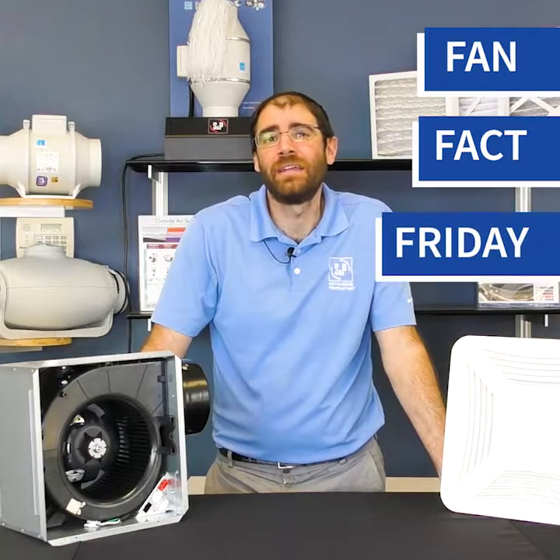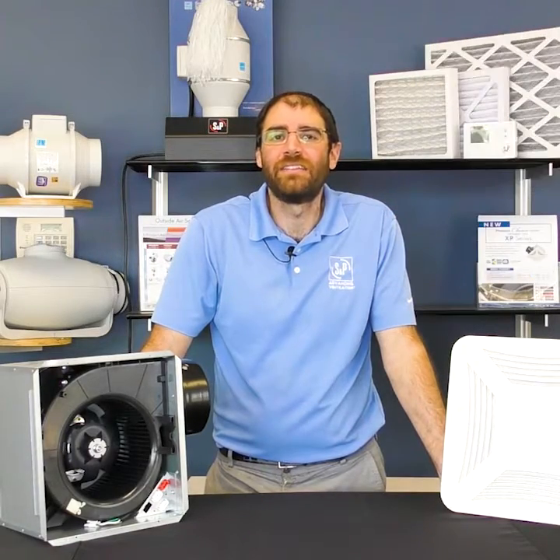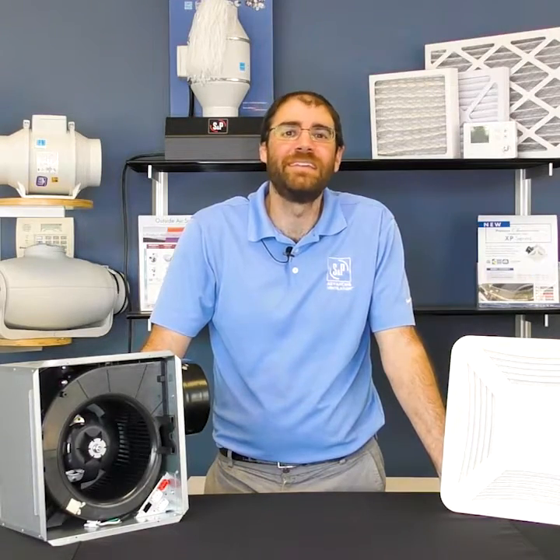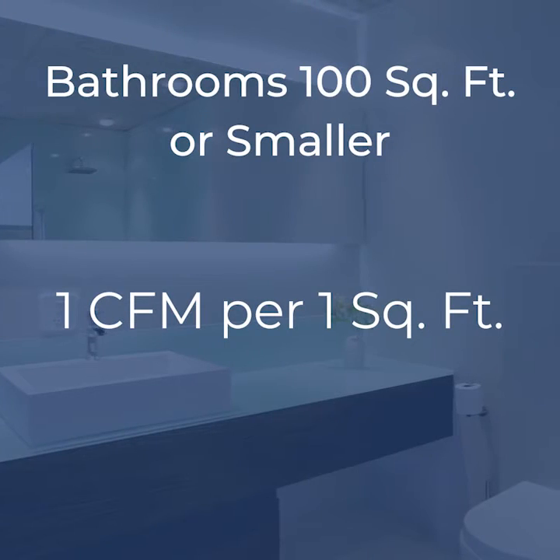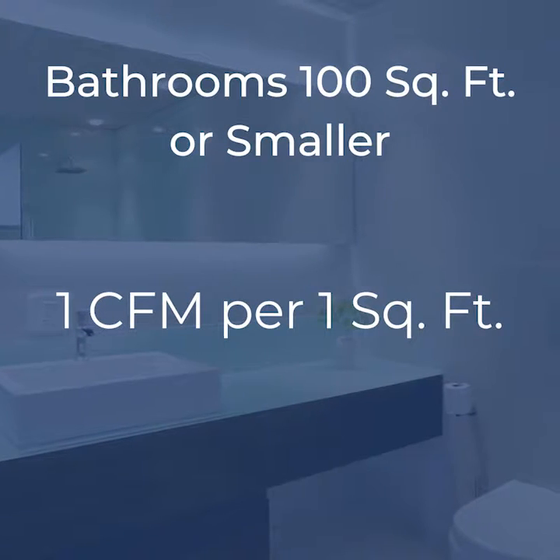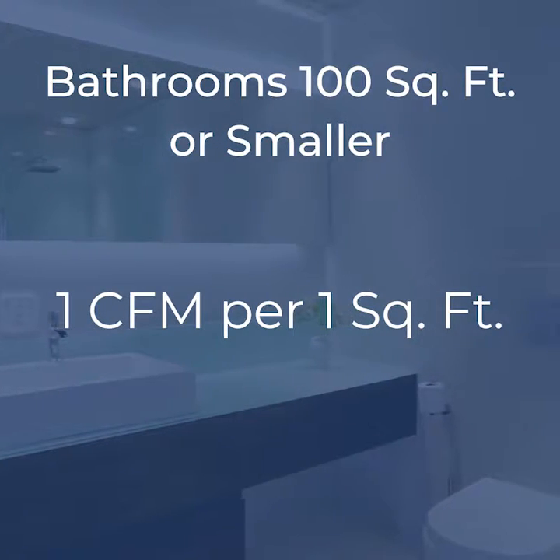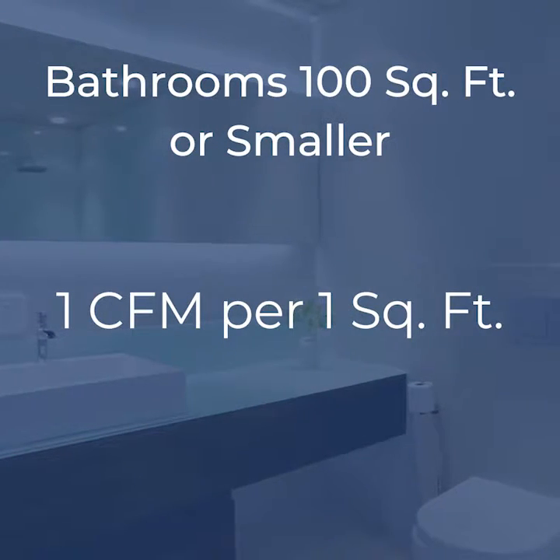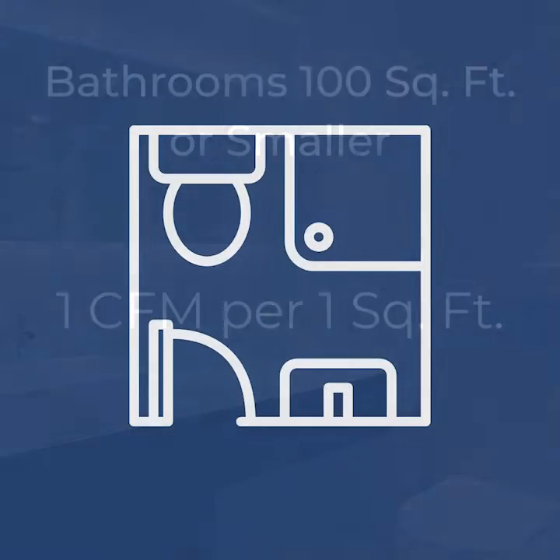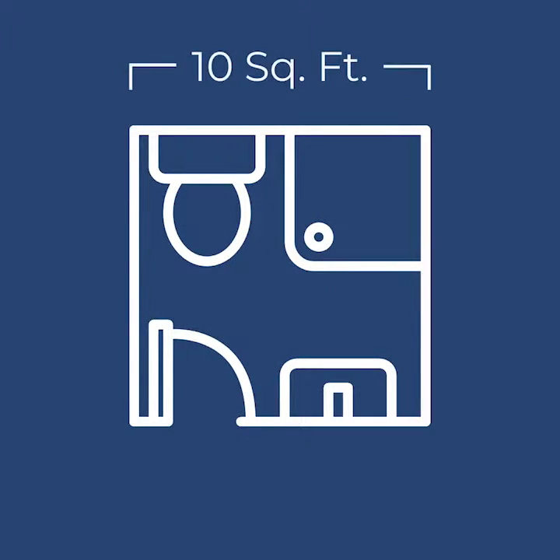Hi, I'm Daniel Grapp, S&P USA's Residential Product Manager. Today is FanFact Friday and we're learning how to calculate the CFM needed in the bathroom. The standard rule of thumb for bathrooms 100 square feet or smaller is 1 CFM per square foot. To find the square footage of your space, multiply the length of the bathroom by the width.